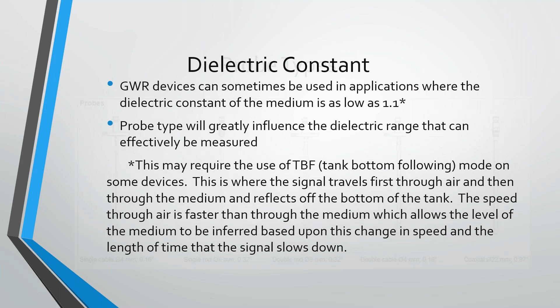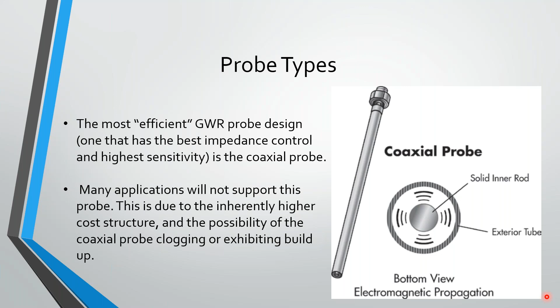Probe types. Probe type is very important when you're selecting a guided wave radar device. So, there are single cables, double rods, coaxial, and all of these have their uses and have their applications. Now, the most efficient one is the coaxial probe. This is going to give you the best impedance, the highest sensitivity. If you can use the coaxial probe, that's your better way to go when you're doing guided wave radar. However, they are more expensive, and depending on what the material is within that vessel, they may be subject to clogging. I mean, if this were a vessel full of corn syrup, this would not be a good probe for that.